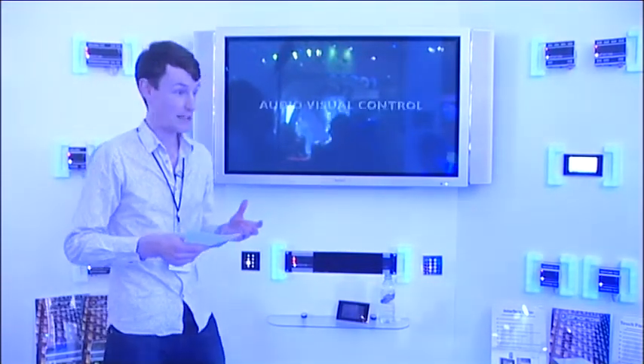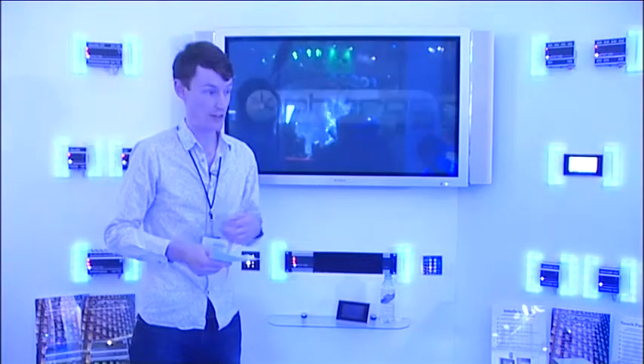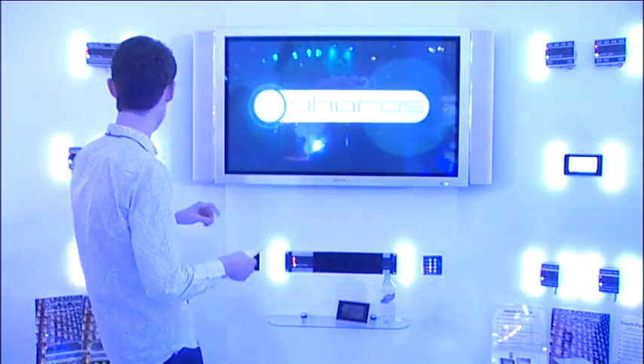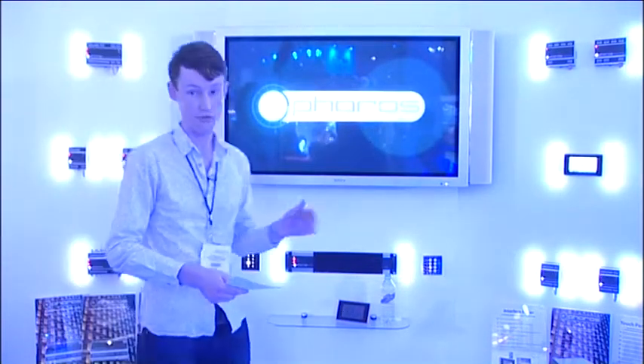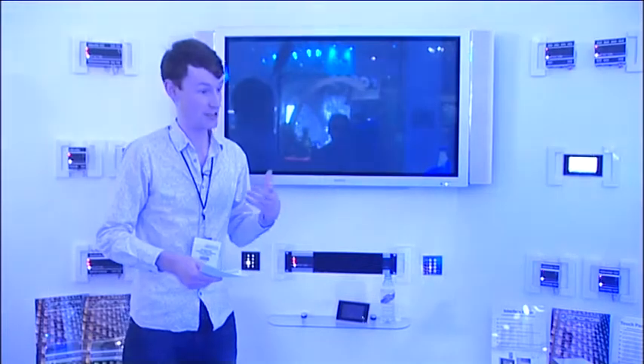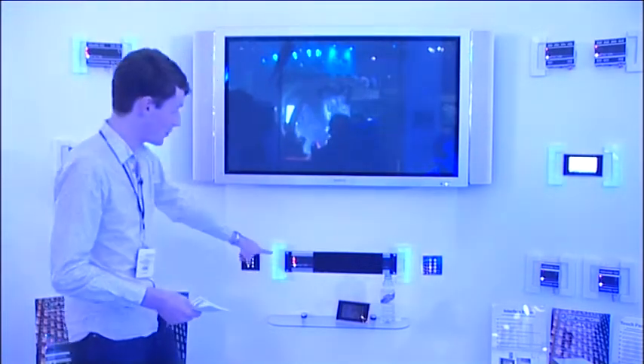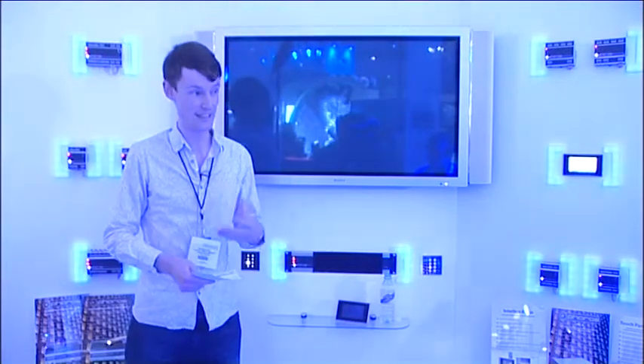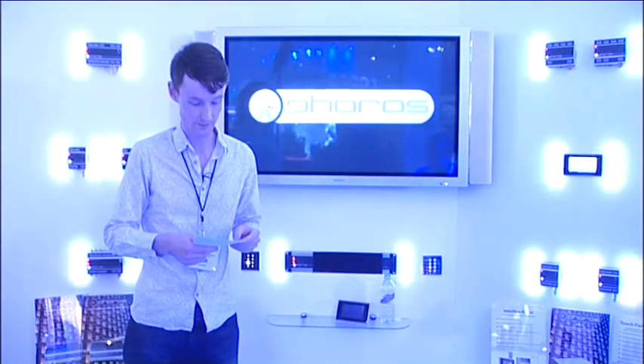The RIO D is compatible with all our lighting controllers, the LPC 1, 2 and 4. The LPC is this one here, where the number is the number of DMX universes. They can each handle up to 16 RIO Ds, and the LPCX down here can handle up to 100 RIO Ds, so that's 6,400 ballasts.